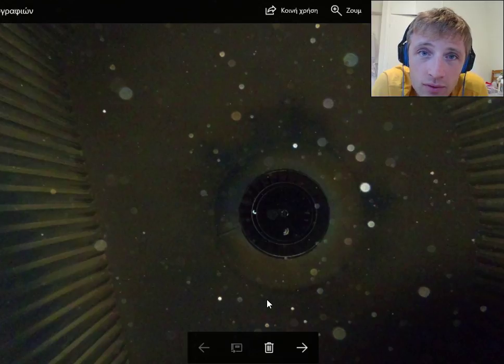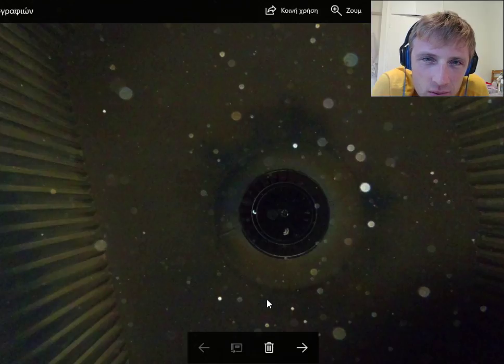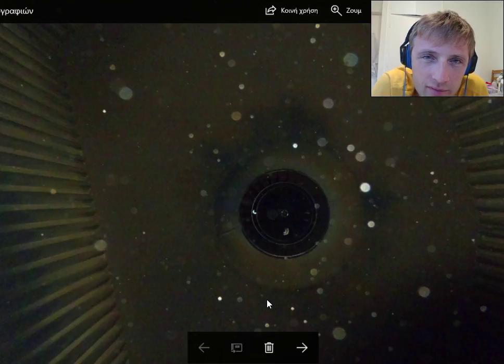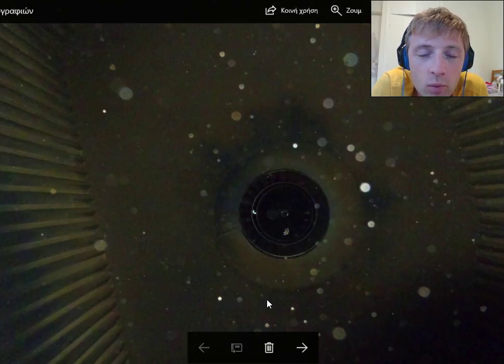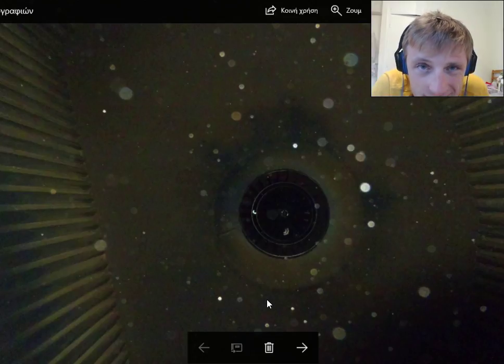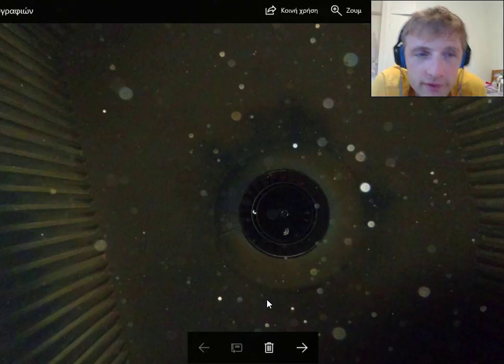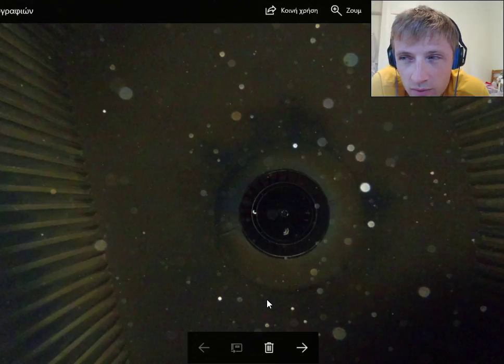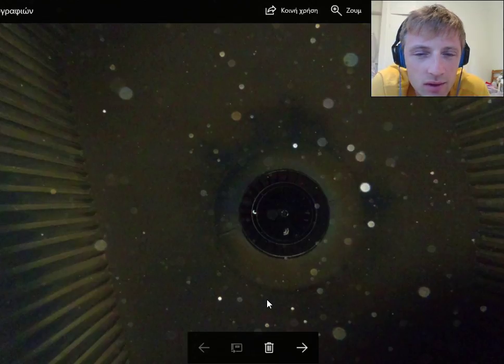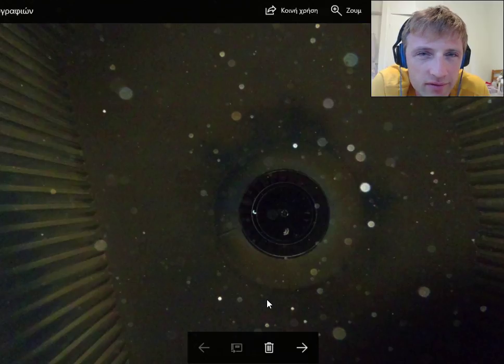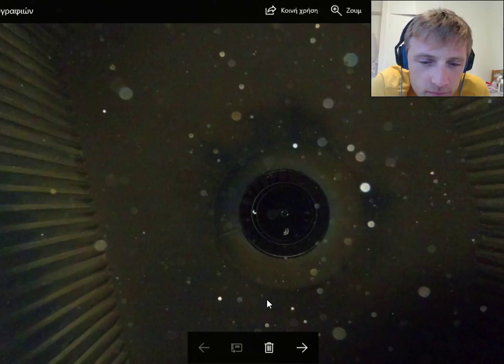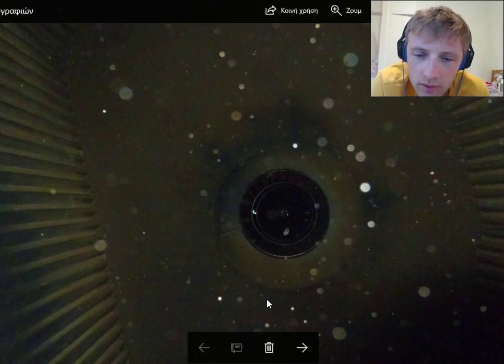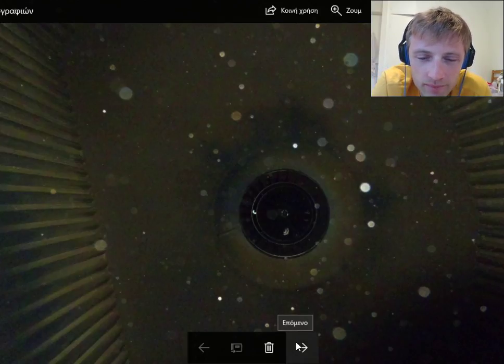The boiler metal inside and the water is very hot and has big thermal quantity. The quantity of water is also a lot, and it needs about one to two days. Also, at one point when the boiler is about one bar or one and a half bar, you need to open the vent valve so the boiler will depressurize.